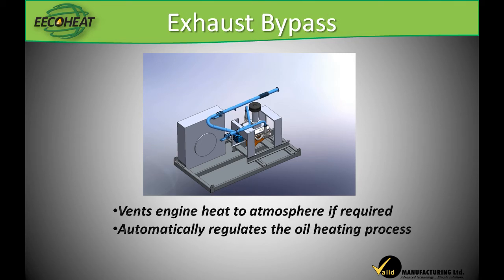The next addition is of major importance in making sure that there is never an interruption to the power-producing capabilities of the engine. Flow from the exhaust manifolds is combined and directed to a bypass diverter system that, if necessary, will allow the engine exhaust to be vented out to atmosphere just as it does on the standard engine. During normal operation, the bypass remains closed, directing engine exhaust into the EECOHEAT system. It will, however, automatically open to vent any excess heat being generated by the recovery system that is not required by the oil heating system.